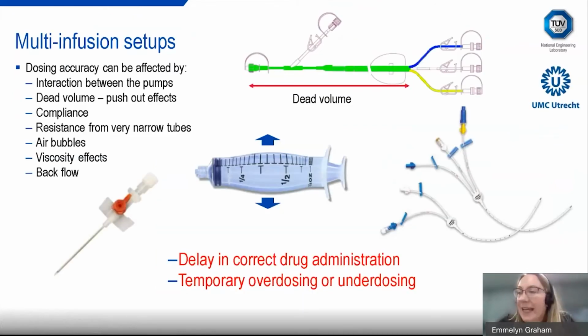So some of the issues that we can get with multi-infusion setups and what affects the dosing accuracy: you can actually get different interactions between the pumps. So if you change the flow rate on one pump, it can actually affect the drug delivery from another pump. You can get what we call the dead volume effect, and this causes push-out effects. So in the image at the very top of the screen, we've got blue, clear and yellow drugs, which are coming from syringes and are then being mixed into a single line before flowing into the patient. So the dead volume is actually the volume in the commingled or mixed infusion line before it reaches the patient. And I'll come on to talk about that and have some animations to describe why this can be an issue and what the push-out effects are.